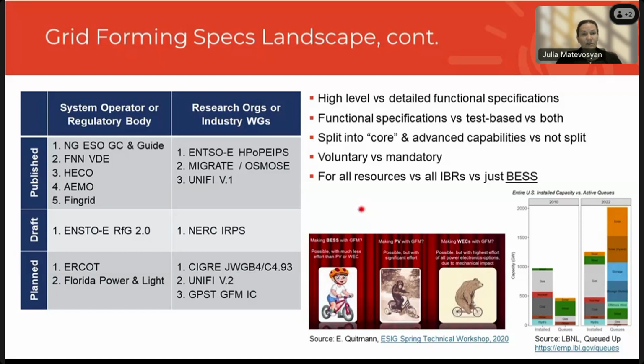There are functional specifications versus test-based specifications. So there is a set of tests that is defined, and the model is subjected to the tests. And if it passes certain criteria, then it's considered grid forming, and it's passing grid forming requirements. And then there are specifications that have both. Some specifications are split into core and advanced capabilities, where core capabilities are expected from all grid forming inverter-based resources, and advanced capabilities are ones that maybe only several inverter-based resources in the area are supposed to comply with. Some are not split like that.